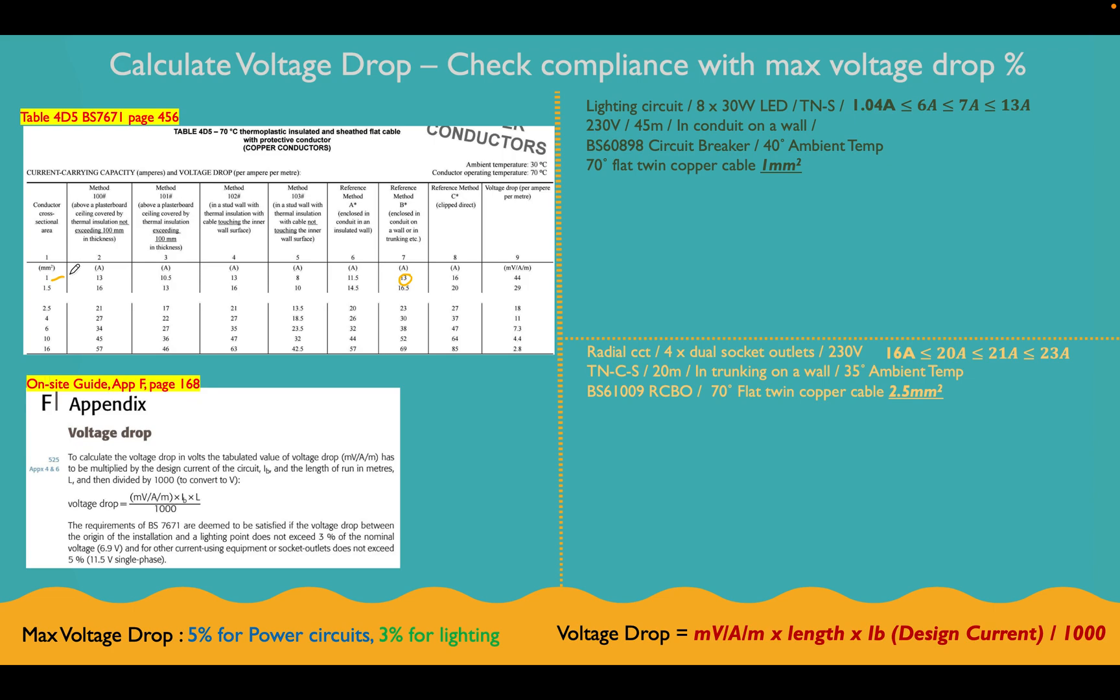So when we're on this table, we can stay here and we can get our millivolt amp per meter value, which is what we need for our voltage drop calculation. So when we've selected 1mm, we can come across and we can get in this side of the table down here, we can actually select our millivolt amp per meter rating, which in this case is 44. So for our lighting circuit, it's 44 millivolt amps per meter. Let's leave it there, and we're just going to come back to that in a minute.